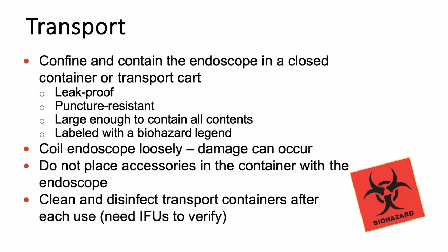When we transport the scopes, we want to make sure that we confine and contain them in a closed container or transport cart. Whatever we use to transport has to be leak-proof, puncture-resistant, large enough to contain all the contents, and labeled with a biohazard legend. It has to be big enough so we can loosely coil the endoscope so we don't damage the fiber optics in it. We shouldn't place accessories in the container because they could damage the scope. And the container has to be cleaned and disinfected after each use.